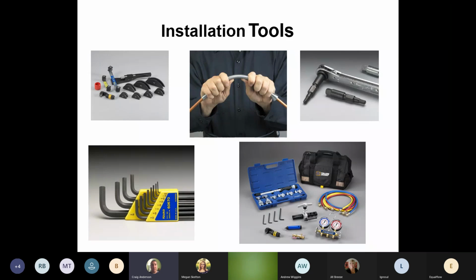Other installation tools, pipe benders, spring benders, Allen keys. We have the little Ritchie service wrench over here that's great for our service valves. When you're working on your service valve, always open it up with a standard Allen key first, then go to your ratchet wrench. Not all the valves will allow that ratchet wrench to fully get into the service valve, and you're going to cause stripping. We've just heated this service valve, and I'm not going to say everyone, but some of these wrenches, you will not get deep enough and you're going to strip that service valve. So it's not fun to change it. So always start it off with a standard Allen wrench and then go to your ratchet service wrench. You're going to save some headaches. If it's never happened to you before, that is great. But when it does happen, it ain't pretty on a brand new unit when you're outside.